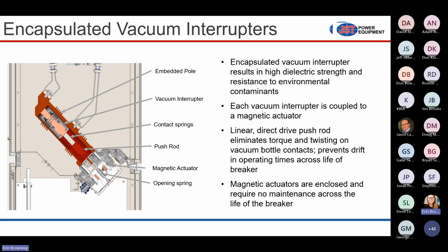And this is the same module that we use in our indoor switchgear. So we took the module, put it in the outdoor breaker, and tilted it slightly because we have incoming line and outgoing line connected to the top and bottom of the vacuum bottle. Tilting it gave us the clearances that we needed to meet BIL, and it makes better use of space for the overall cabinet design.